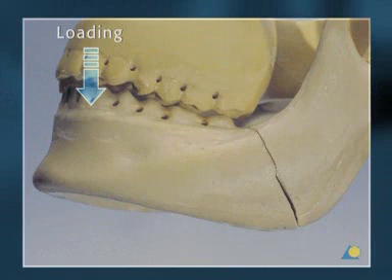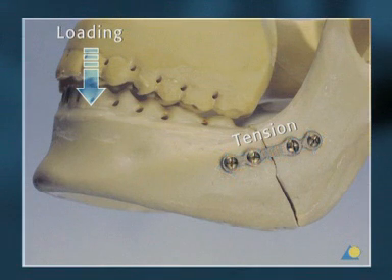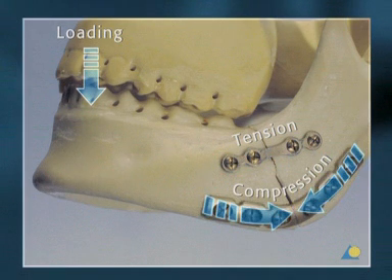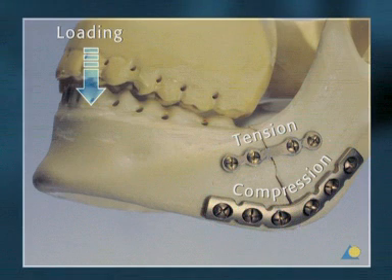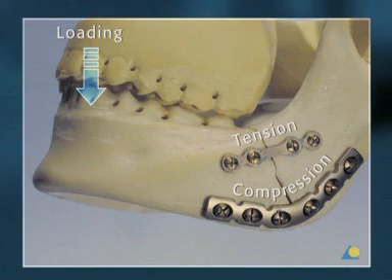Loading across a mandible angle fracture leads to tensional forces at the upper border, which are borne by a 2.0 mandible mini plate, and compressive forces at the lower border, which can be borne by the 2.4 universal fracture plate and the fracture surfaces. Therefore, load sharing takes place when the load across the fracture is shared between the fixation system and the fracture surfaces.